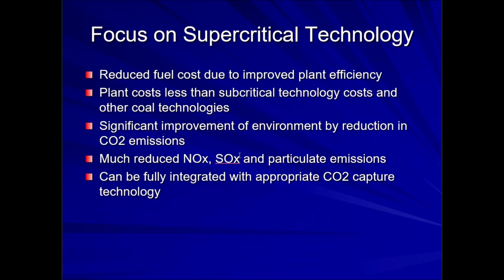Next, focus on supercritical technology. The government is shifting towards supercritical technology based units to enhance efficiency of power generation and reduce coal consumption and GHG emissions from coal fired power plants. Units based on supercritical technology have higher efficiency than conventional subcritical technology, thereby ensuring lower CO2 emissions. Supercritical units are designed with higher steam parameters of 247 kg per centimeter square with temperature of 565 to 593 degree centigrade. Due to the improved thermodynamics of expanding higher pressure and temperature steam through turbines, they attain higher efficiencies than traditional subcritical power plants.